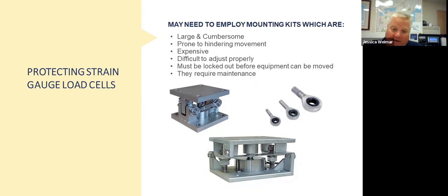So what you're looking at here is basically a mounting kit that you can purchase from the strain gauge manufacturer, or in some cases people manufacture these themselves, but the concept is the same. This actual bracketry that you see around it is designed such that any kind of a load that's out of the normal weighing plane, and think about the normal weighing plane is going to be pushing down directly on this top plate. This would be your fixed plate on the bottom. Okay, and the cell is inside here, and it's actually free floating. It's not physically attached to the top or bottom.